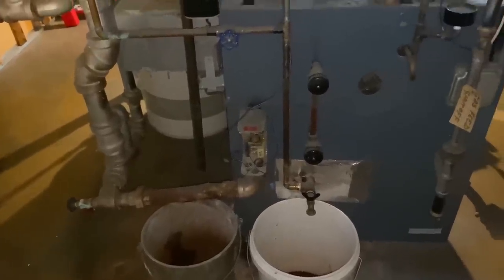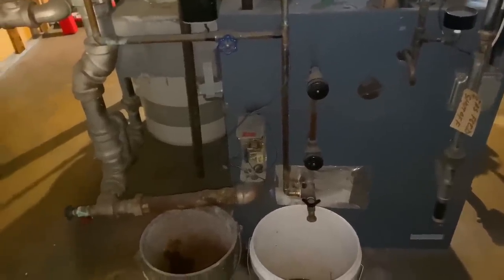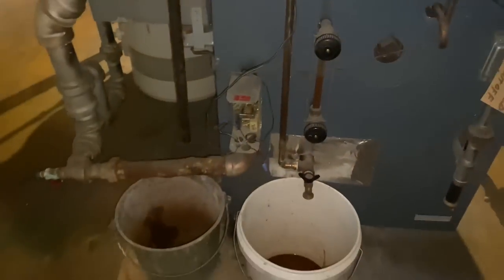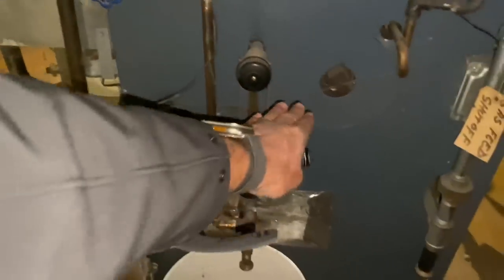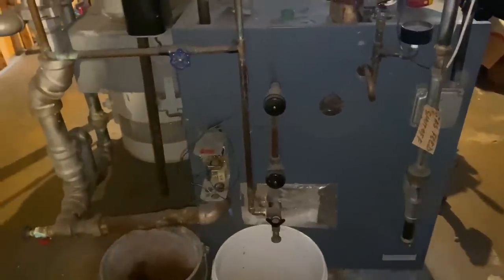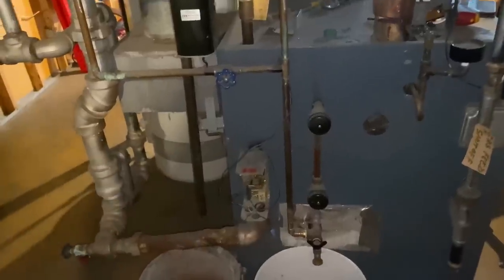What's happening is that for an unknown amount of time, a hole or crack developed above the water line. You can see there's a sight glass here with a water line visible, so that's the water line of the boiler. Somewhere above there is a crack, and that's evident by the steam we saw earlier and the white smoke visible on top of the chimney. The chimney is also disintegrating - it should be lined or redone.